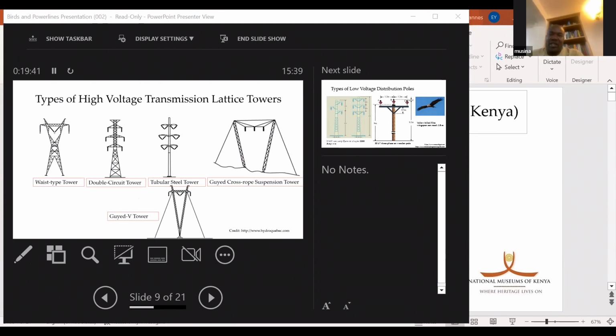I want to point out that in critical habitats where birds might collide with these transmission lines, it's recommended that the guyed cross-rope suspension tower be used, because it has the least chance of providing perching areas for birds. The problem is when birds perch on them and try to nest, we get problems with collision and electrocution.